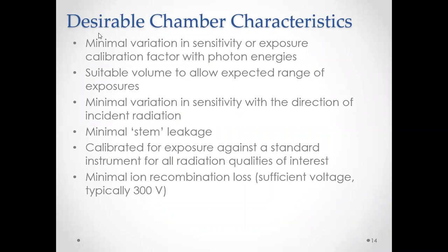Desired chamber characteristics include: minimal variation in sensitivity or exposure calibration factors with photon energies; suitable volume to allow the expected range of exposures; minimal variation in sensitivity with the direction of incident radiation; minimal stem leakage; calibration against a standard instrument for all radiation qualities of interest; and minimal ion recombination loss — ensuring sufficient voltage so that all created ions are counted.